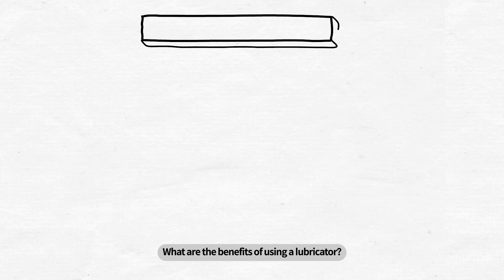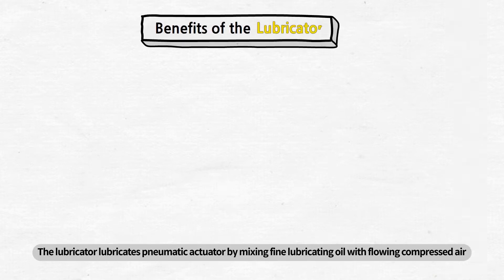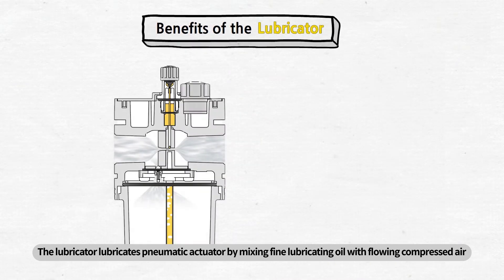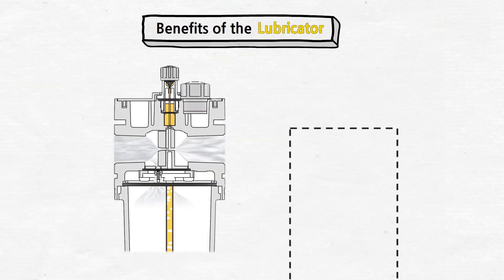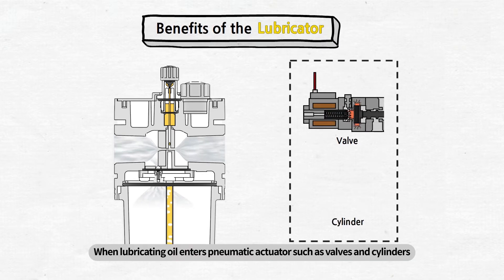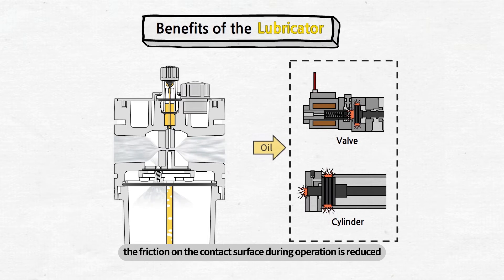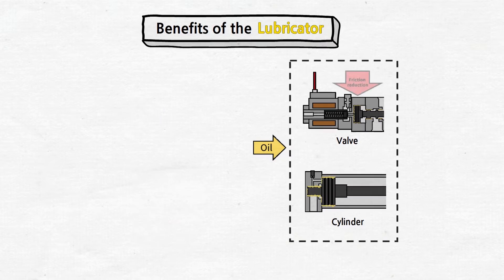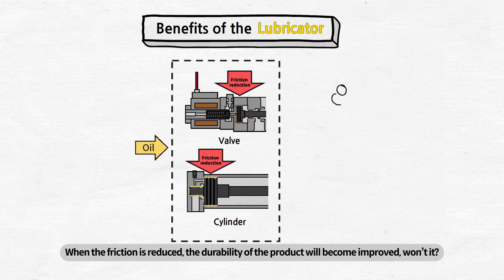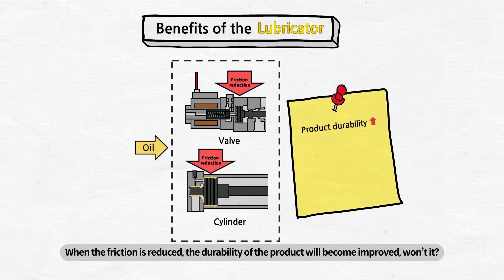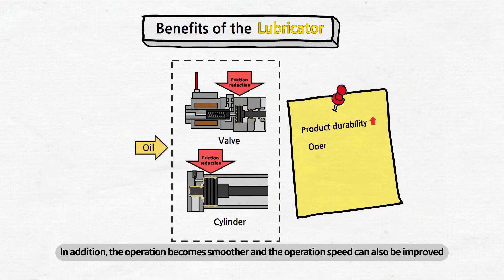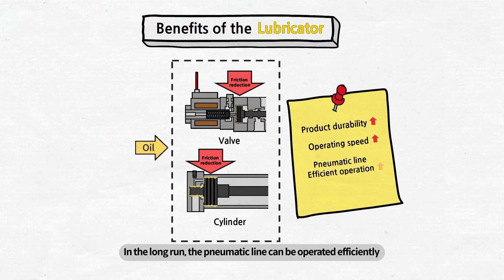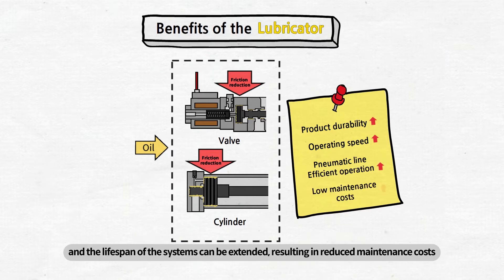What are the benefits of using a lubricator? The lubricator lubricates pneumatic actuators by mixing fine lubricating oil with flowing compressed air. When lubricating oil enters pneumatic actuators such as valves and cylinders, the friction on the contact surface during operation is reduced. When the friction is reduced, the durability of the product will become improved. In addition, the operation becomes smoother and the operation speed can also be improved. In the long run, the pneumatic line can be operated efficiently and the lifespan of the systems can be extended, resulting in reduced maintenance costs.